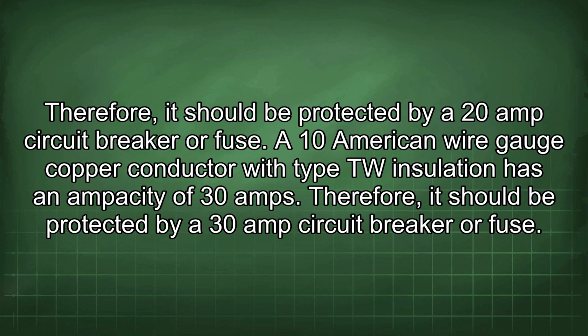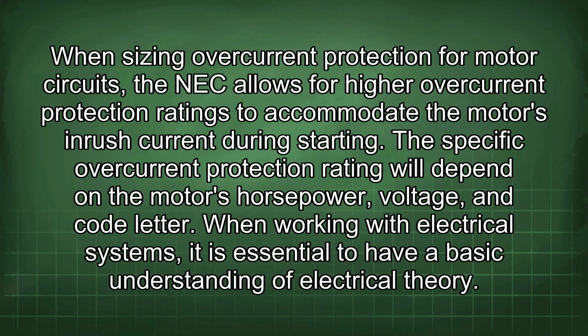Therefore, it should be protected by a 20 amp circuit breaker or fuse. A 10 American wire gauge copper conductor with type TW insulation has an ampacity of 30 amps. Therefore, it should be protected by a 30 amp circuit breaker or fuse. When sizing overcurrent protection for motor circuits, the NEC allows for higher overcurrent protection ratings to accommodate the motor's inrush current during starting. The specific overcurrent protection rating will depend on the motor's horsepower, voltage, and code letter.